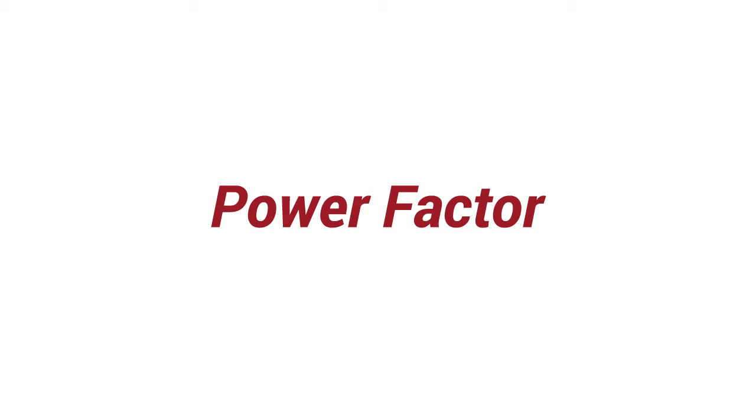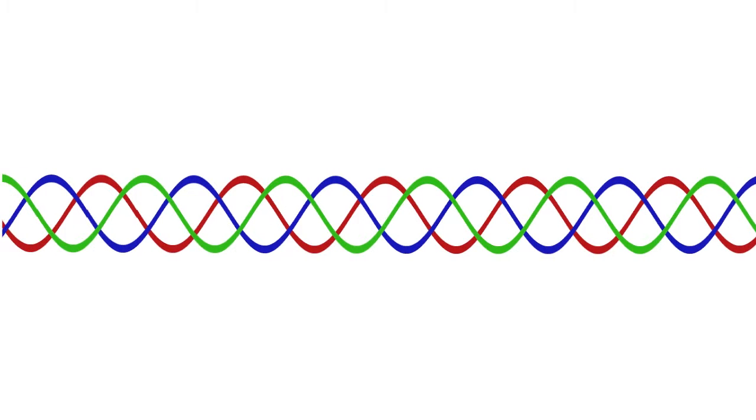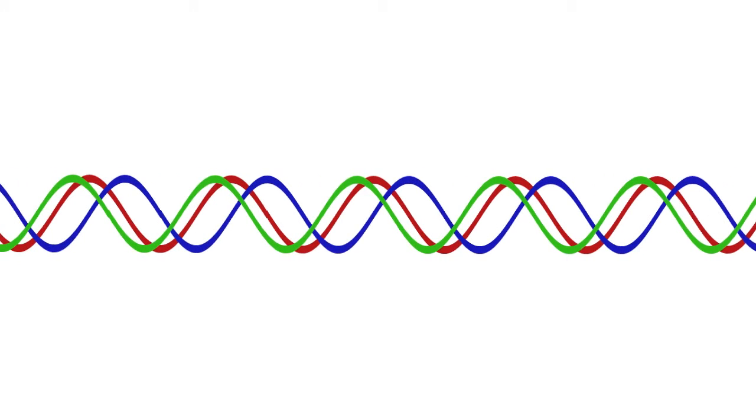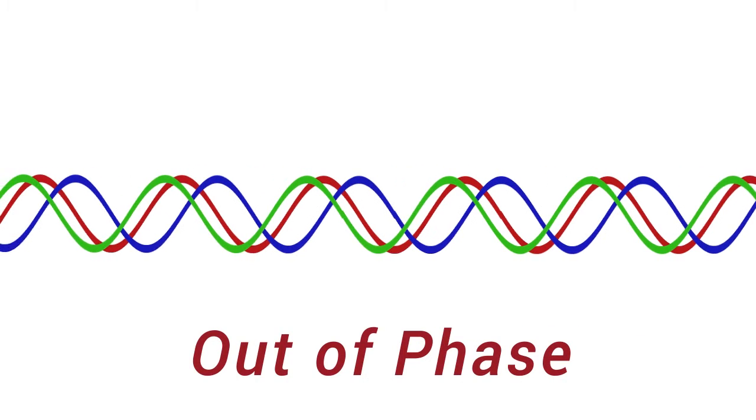Power Factor is a measure that allows an operator to make sure the power coming into their facility is in phase. It is calculated as the ratio of real power to apparent power. A power factor of less than one means that the voltage and the current waveforms are not in phase.